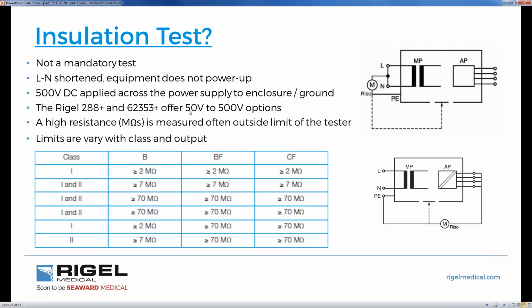We apply either, and the Rigel 288 Plus and 62353 offer a number of ranges, anywhere between 50 volts to 500 volts DC. So between our protective earth and live and neutral common, we apply a large DC voltage of 500 volts DC, and we measure the resistance in megaohms. So it's a high resistance, and we have some of these pass-fail thresholds. The pass-fail thresholds in 62353 have been generally adopted from what you would call accepted levels of resistance. This is from both PAT testing and from production testing.